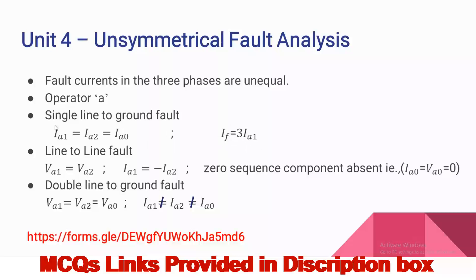For a line-to-line fault (double line fault), positive sequence voltage equals negative sequence voltage; importantly, zero sequence components are absent — I-a0 equals zero and V-a0 equals zero. The positive sequence current equals the negative of the negative sequence current — both currents are in opposite directions. For a double line-to-ground fault (line-to-line-to-ground fault), the sequence voltages are equal: positive equals negative equals zero sequence voltage. The currents are all different — positive sequence current is not equal to negative sequence current, which is not equal to zero sequence current.